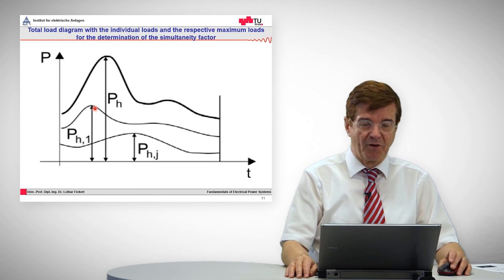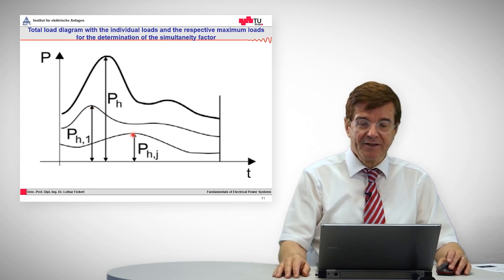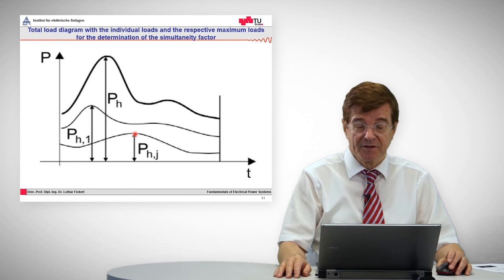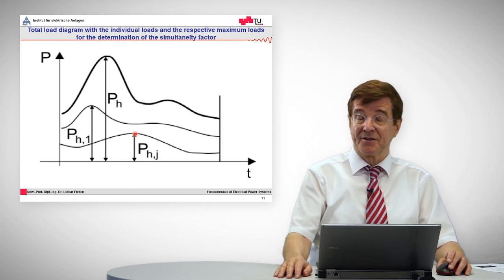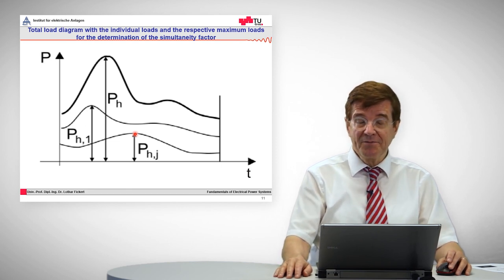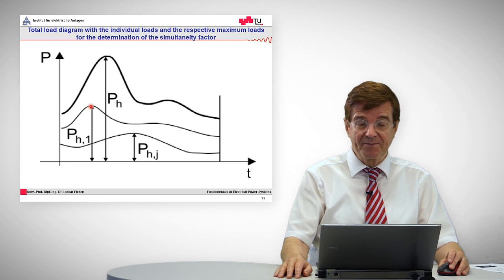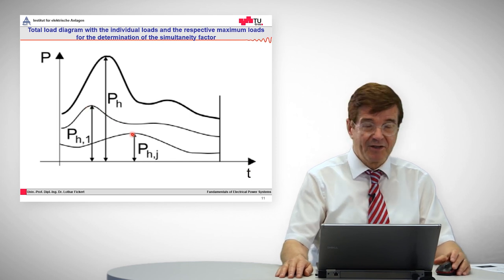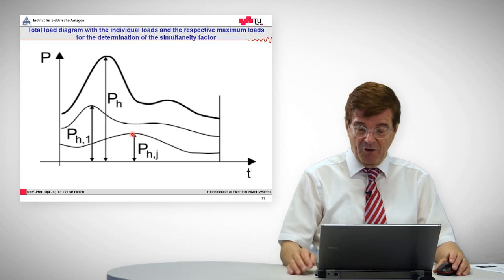another load that has the peak during the daytime, if these are superimposed, the maximum peak is less than the sum of this peak and this peak. So this leads to the coincidence factor which is always below one.